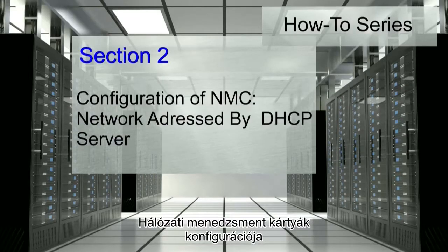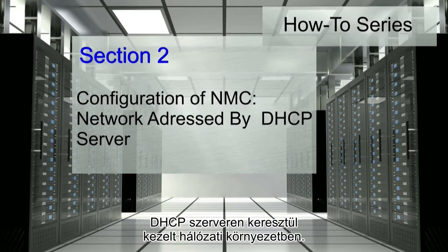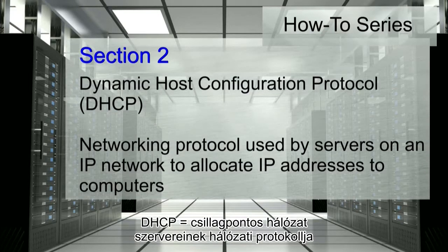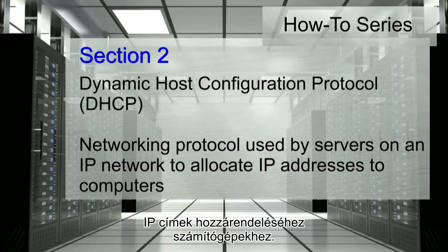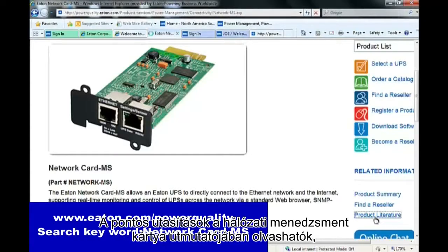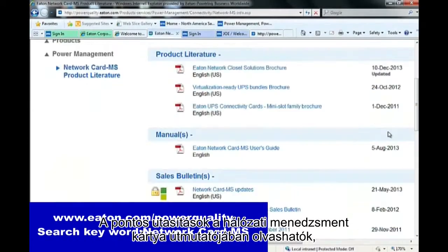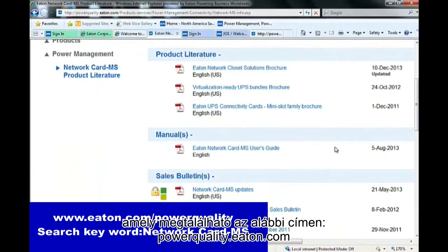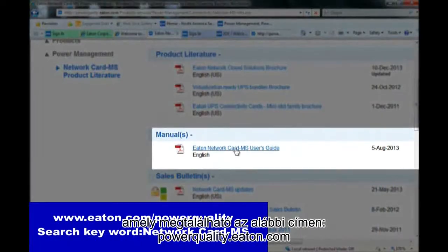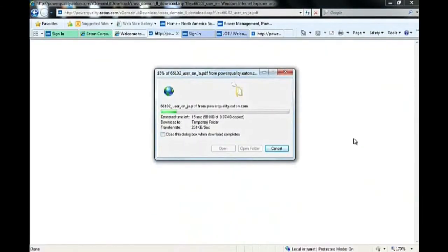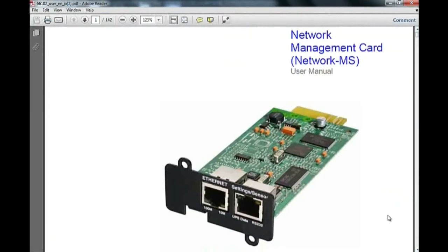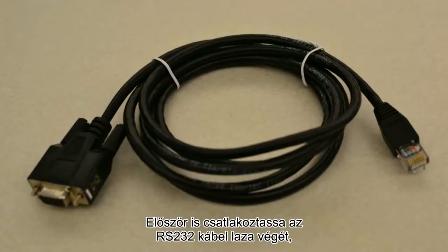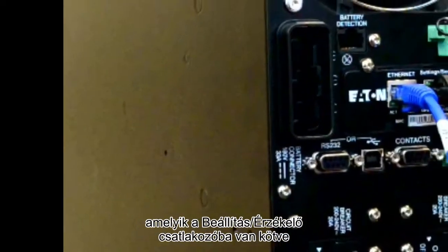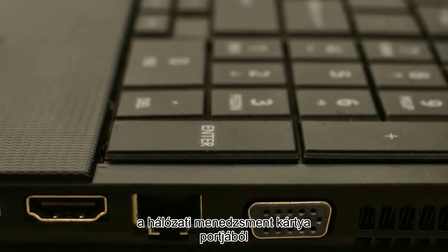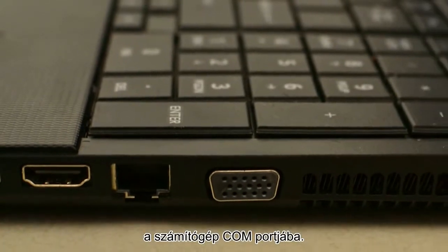Configuration of a network management card within an environment where the network is addressed by a DHCP server. The written instructions can be found in the Network Management Card User Manual located through powerquality.eaton.com. To begin, connect the loose end of the RS-232 cable, which is connected to the setting/sensor port of the Network Management Card, into the COM port of a PC.